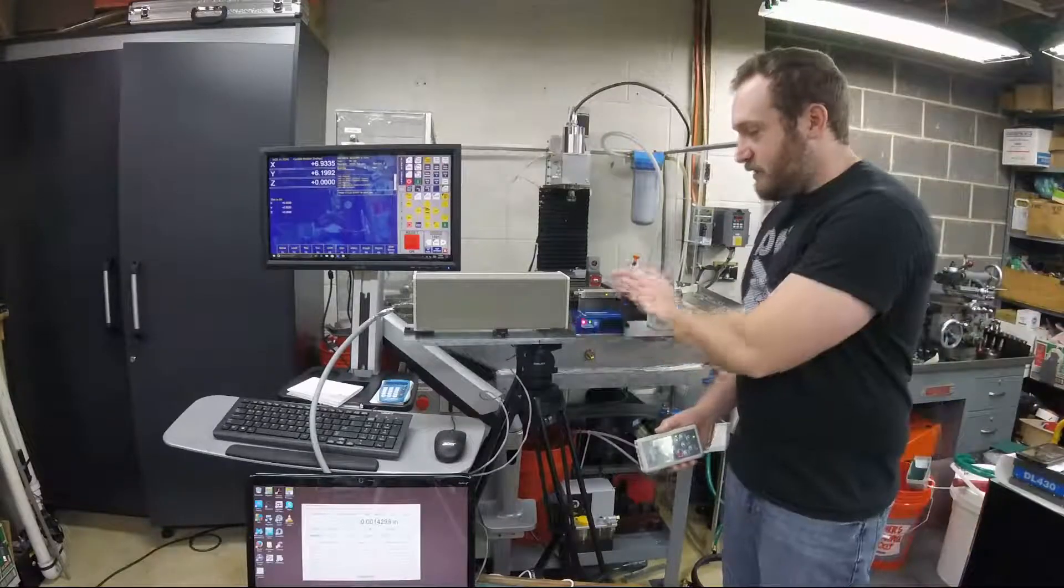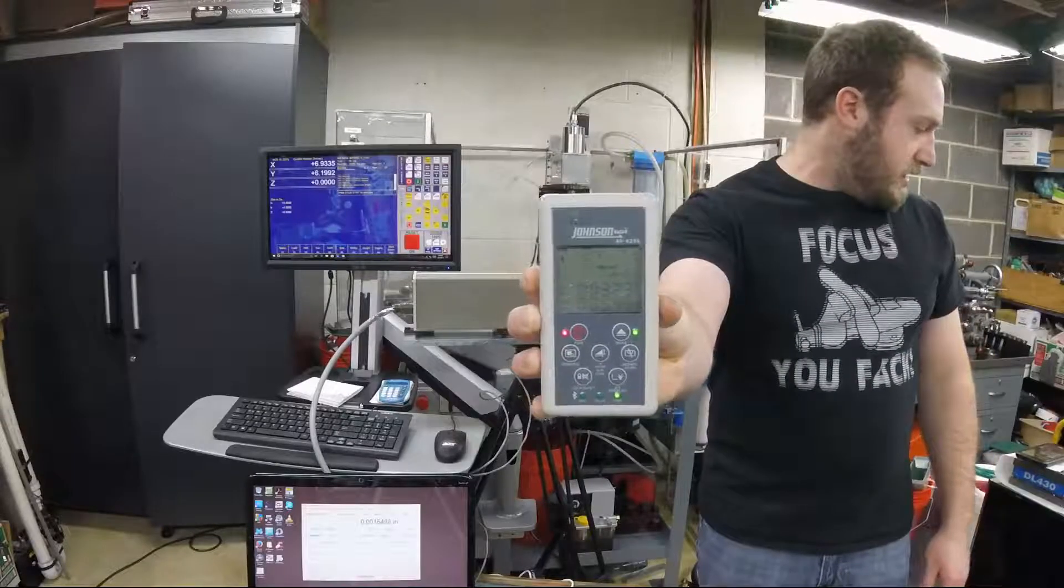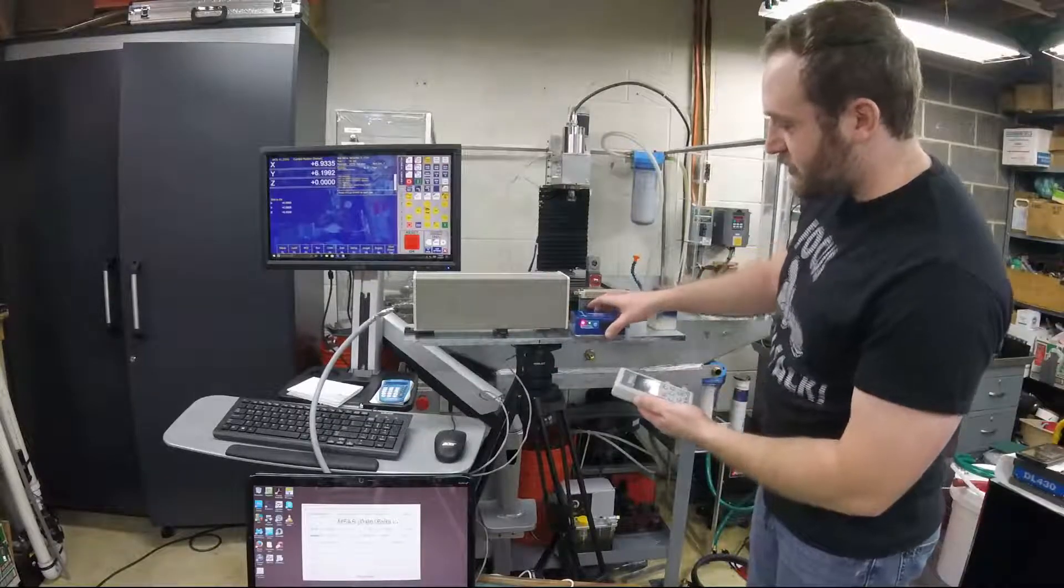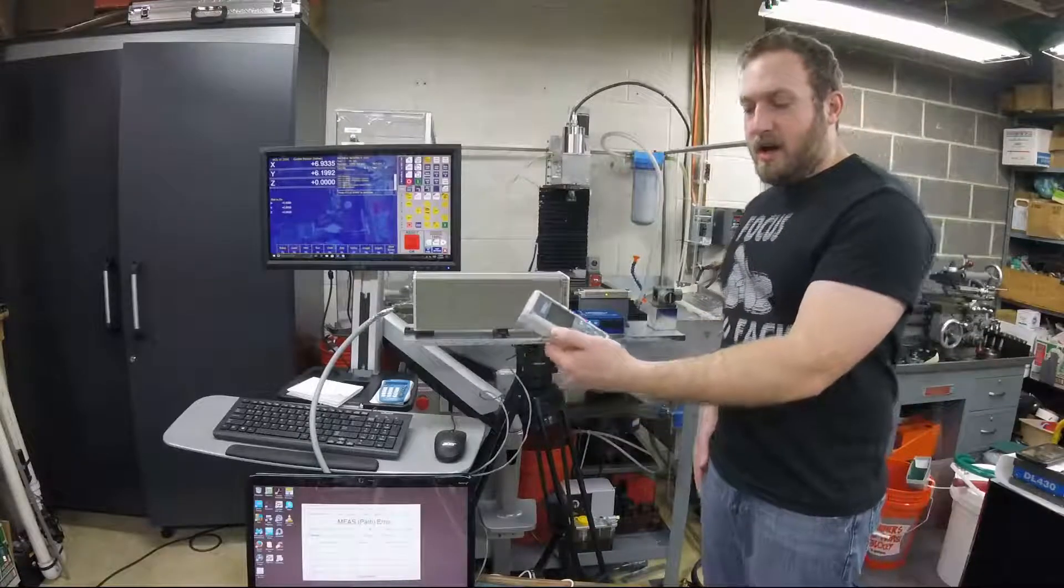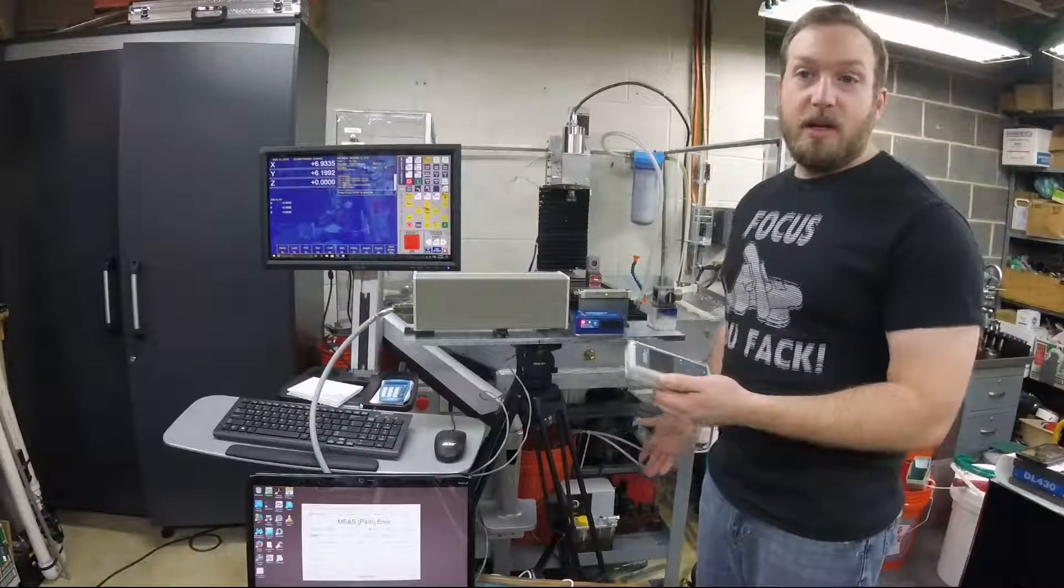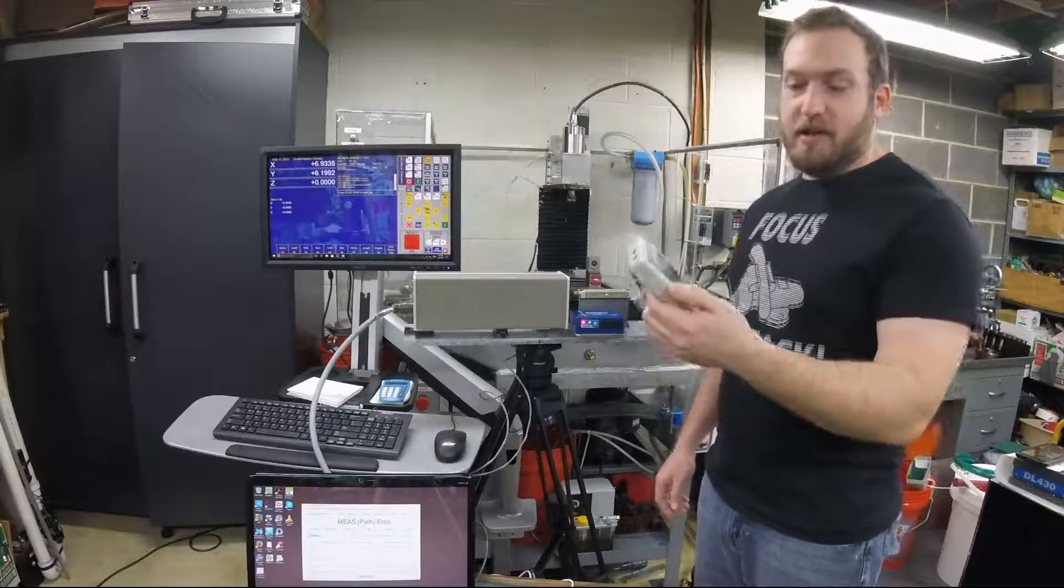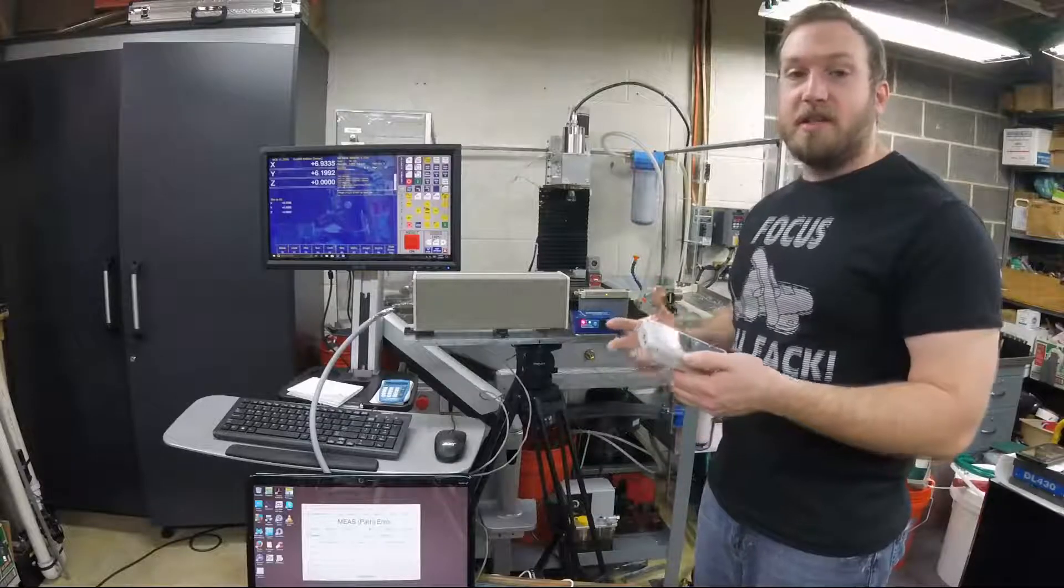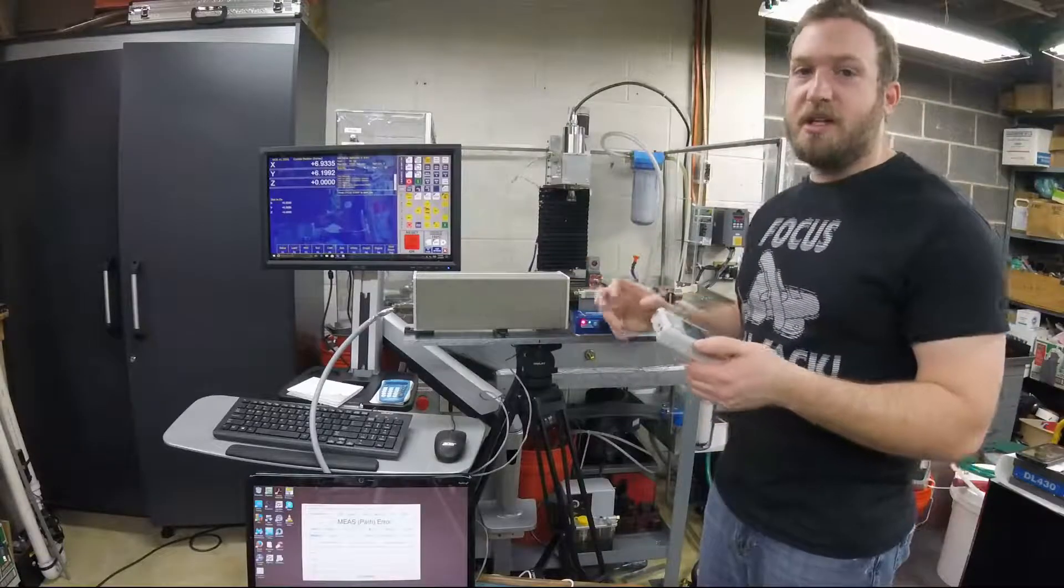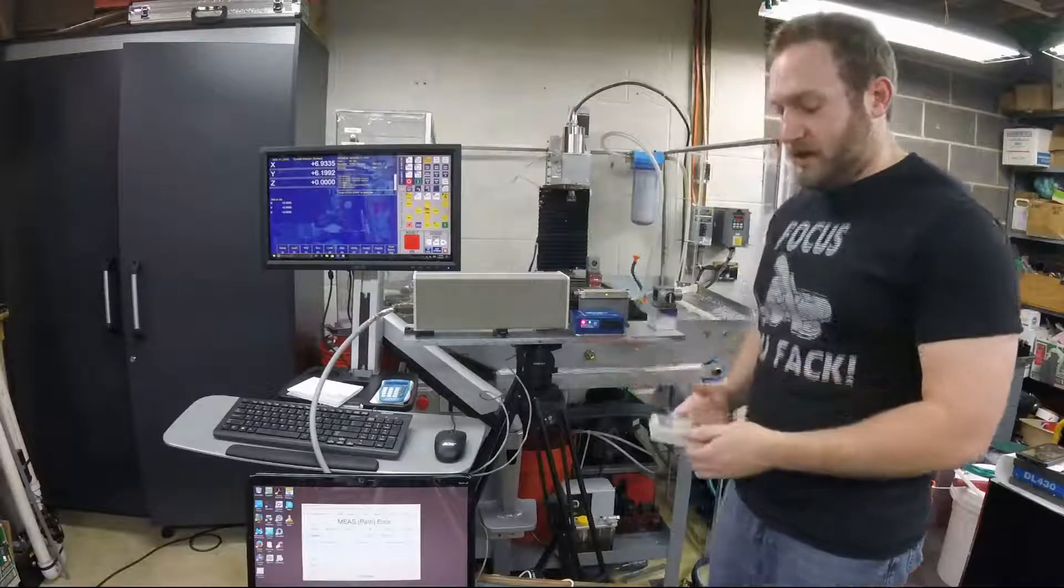Number one is always level that sucker and get it ready. What I use, and I just got it sitting here on the laser right now just to show you, is a Johnson two axes level. So what it looks like, it gives you a Bluetooth display, and it shows you both axes, the X and the Y at the same time, with this controller. So they're Bluetooth enabled. So basically you sit this sucker on the machine, and you level it using the handheld. And what that gives you is a much easier way to do it, because all my leveling, they're on the feet, they're on the bottom. Whereas now I can just sit here with the Johnson in my hand and adjust and get everything in square with both axes at the same time.